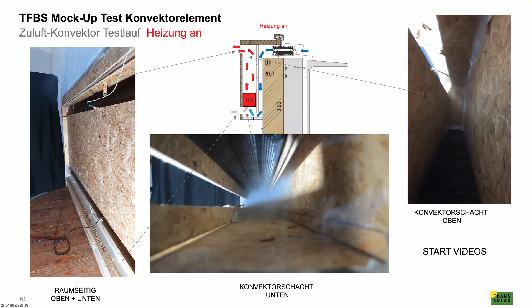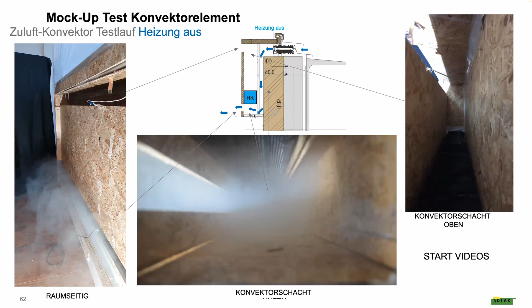The mechanical engineers said, this is all okay, but what happens if, for whatever reason, this convector is switched off? Then it will freeze and break, and we have a problem. So we said, we'll do another movie, and we did. We found out if we don't switch the convector on, the air just comes out at the bottom - doesn't harm the convector, everything's fine, inherent frost protection with no control element needed. And they believed us and said, fine.